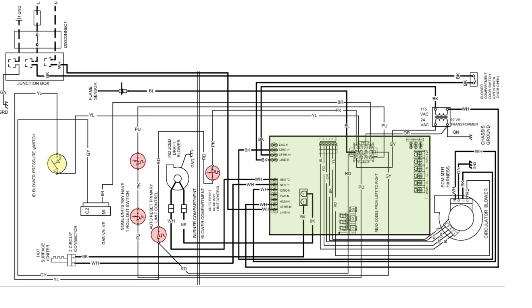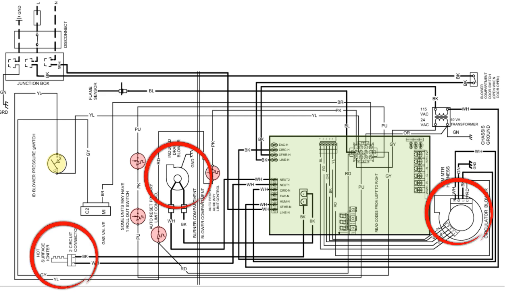High voltage circuits on most of these units, they're almost always going to be parallel. So for a furnace, for example, the inducer draft motor, the blower motor, the hot surface igniter, each one has a power source of its own. The control board can control each one independently.